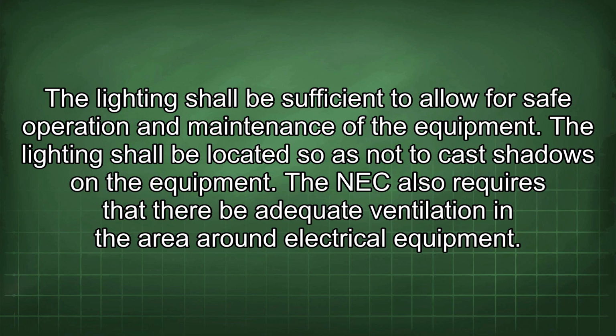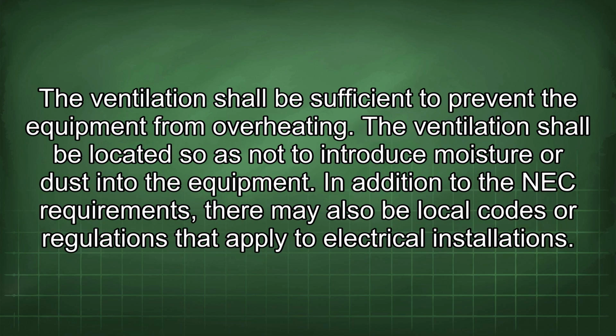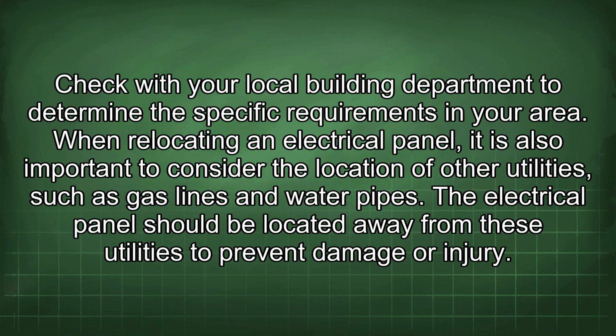The NEC also requires that there be adequate ventilation in the area around electrical equipment. The ventilation shall be sufficient to prevent the equipment from overheating. The ventilation shall be located so as not to introduce moisture or dust into the equipment. In addition to the NEC requirements, there may also be local codes or regulations that apply to electrical installations. Check with your local building department to determine the specific requirements in your area.